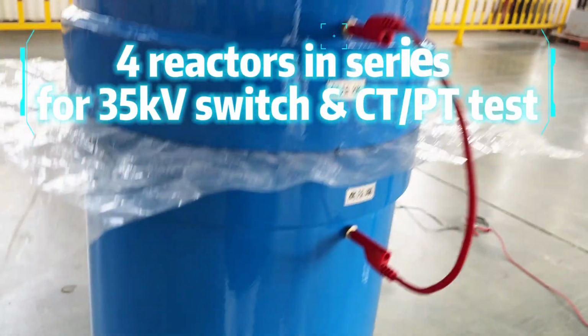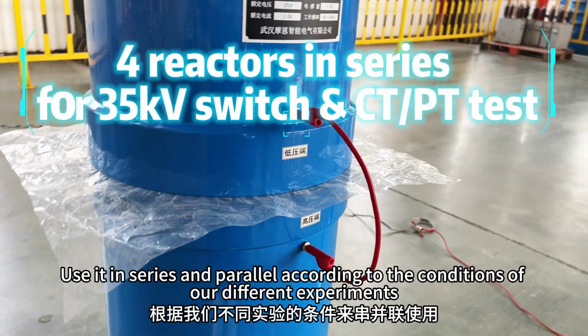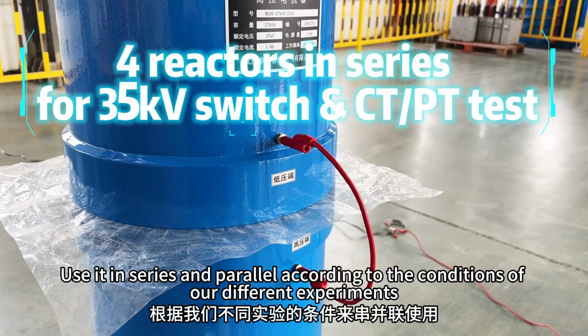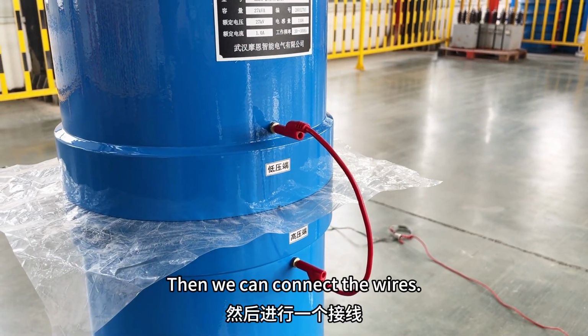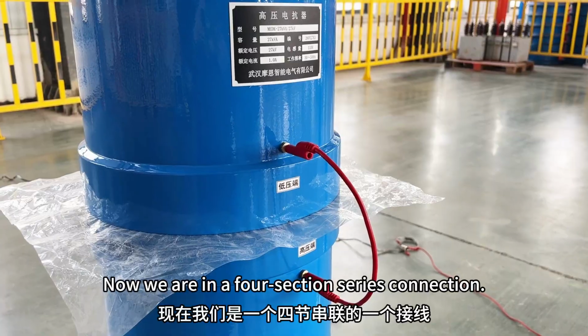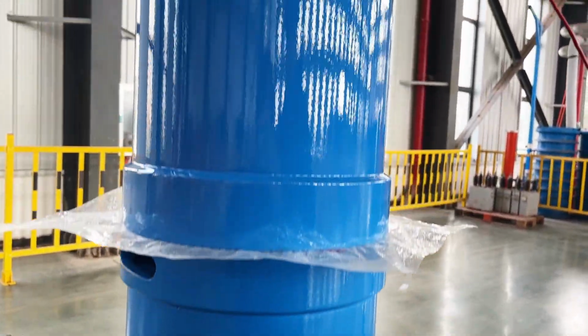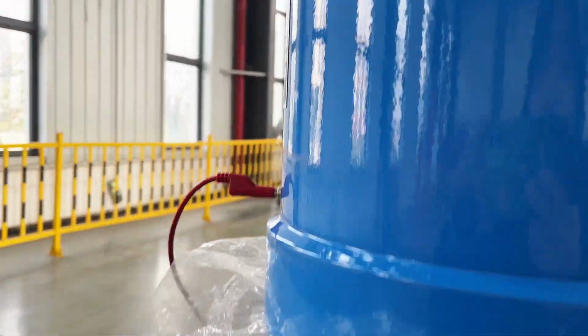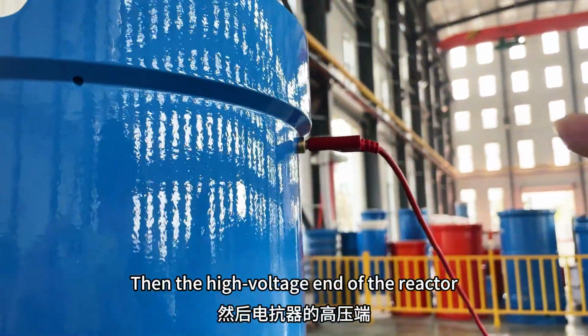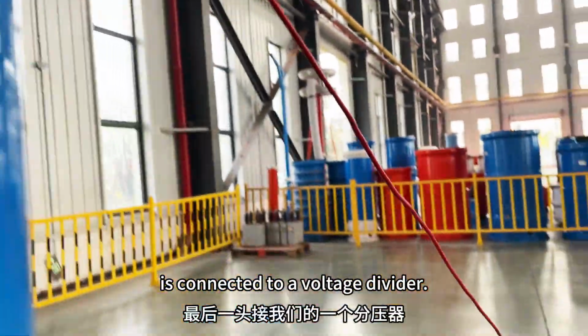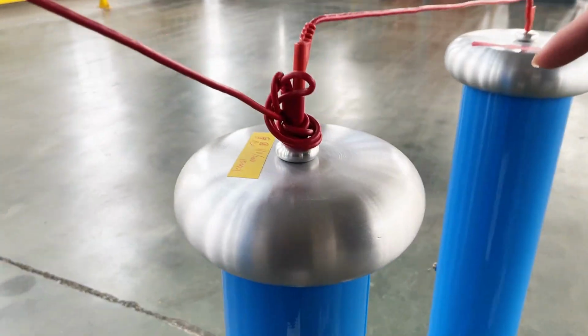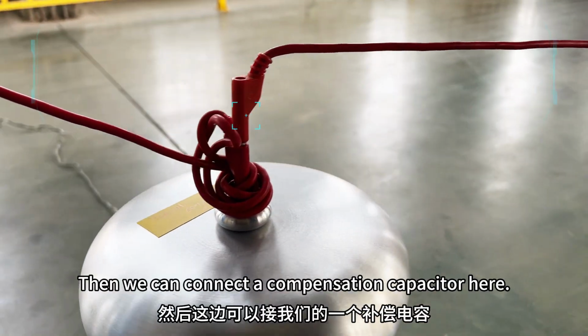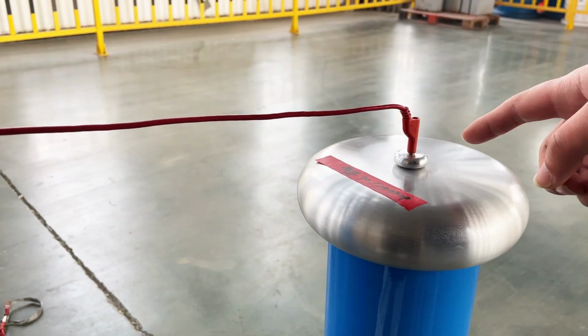Then our reactor. Use it in series and parallel according to the conditions of our different experiments. Then we can connect the wires. Now we are in a 4-section series connection. Then the high voltage end of the reactor is connected to a voltage divider. Then we can connect a compensation capacitor here.